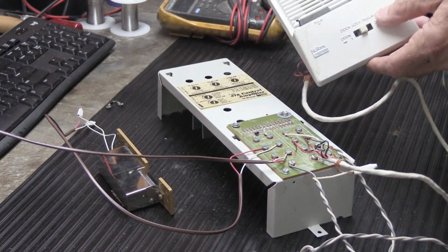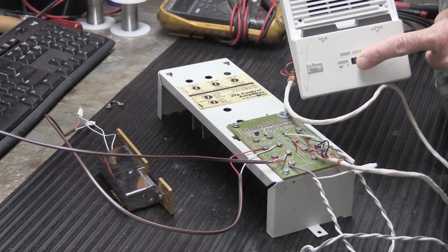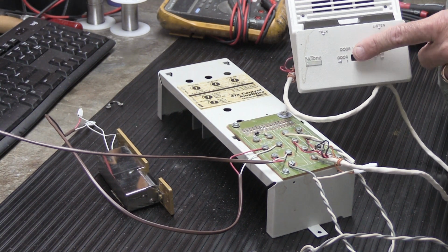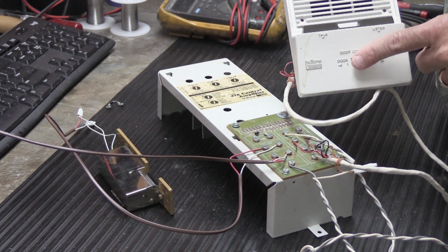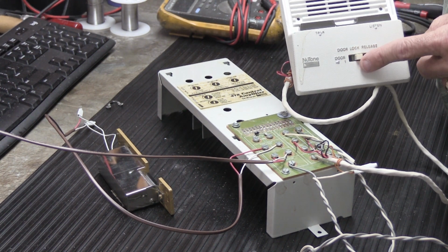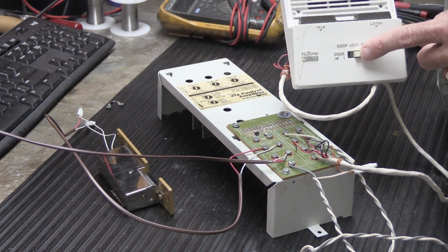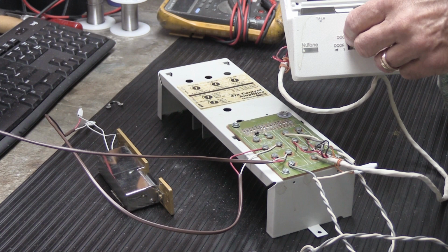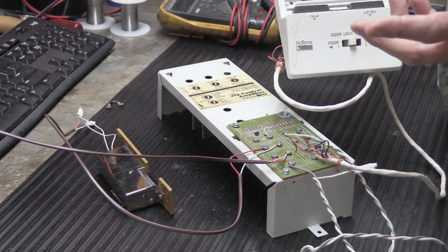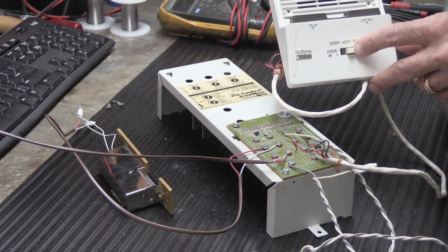It could be a problem with the door release switch on the N45 speaker, that's this one right here, but the odds that 6 of these switches all went bad in the same building at the same time, very rare. Honestly, in the almost 40 years that I've been doing this, I have never had an occasion to replace one of these switches, unless somebody physically attacked it with a hammer and broke it. Other than that, no. They're just a very simple spring-loaded slide switch. There really isn't much to go wrong.